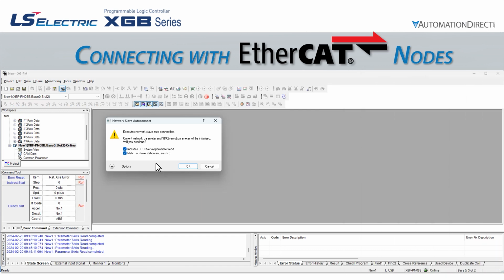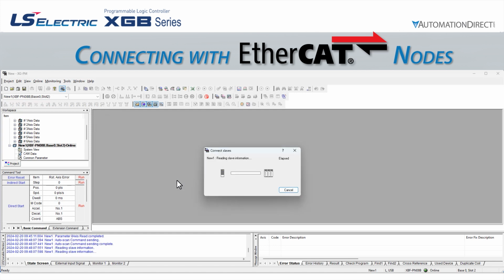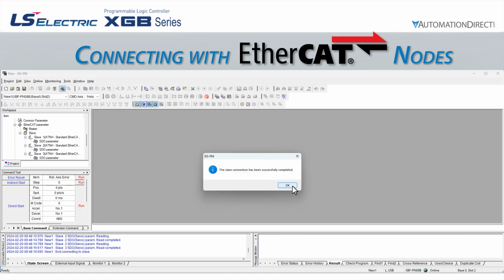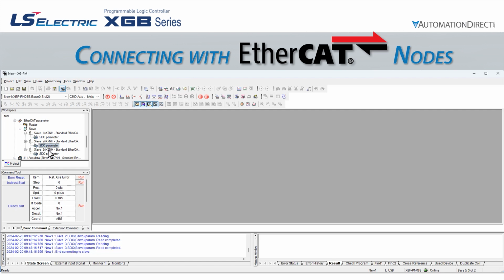In our example, we don't care about the files already in the motion module, so we will make sure the checkbox to read the SDO files from the network, as well as the box for matching the slave station and axis numbers together, are checked. Once we hit OK, the software will scan the EtherCAT network. It then gives us a confirmation message once the process has been completed successfully. We see the 3 slave drives have been added to the project window on the left side.